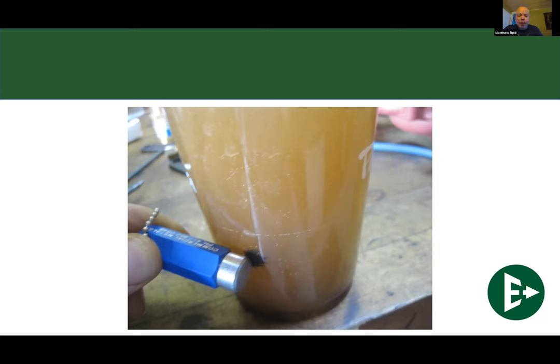The other place a magnet should be inside your system is in this magnetic dirt separator. Protect those expensive pumps and get that magnetite out at a place where it's designed to be serviced from. That's how you can really bring your system to the next level. Because if you don't get it out there, it's absolutely going to stick to those pumps, or worse, to the inside of the heat exchanger. That magnetite is going to do you no favors inside of a heat exchanger.